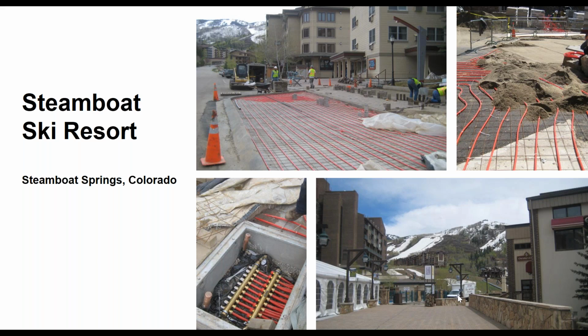If that's not possible and you're using other materials that the pipe would be embedded in, like an insulated foam board with grooves that the pipe's able to snap in, then you'd want to, at least if possible, get the tile system that goes above that as close to the top surface of that heating panel as possible, and eliminate any air gaps would be the only recommendation there.